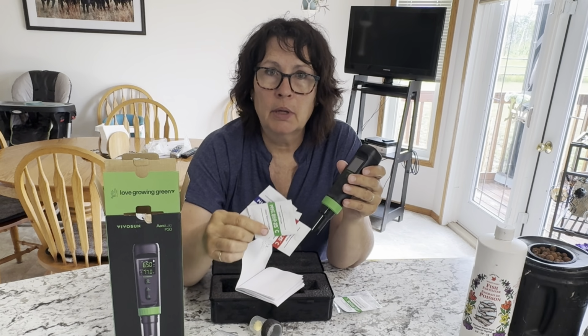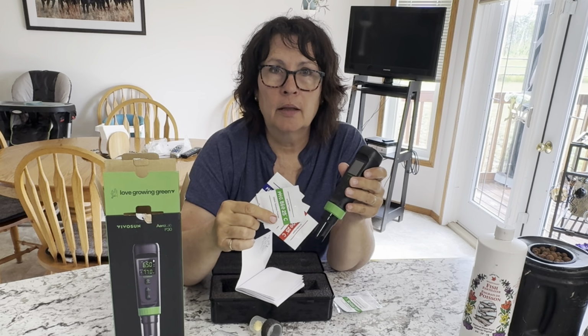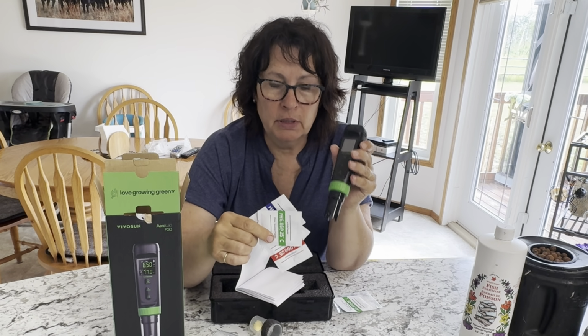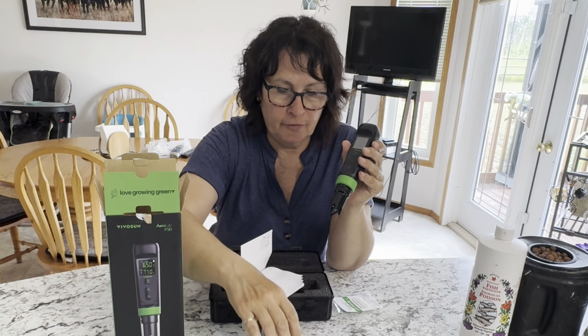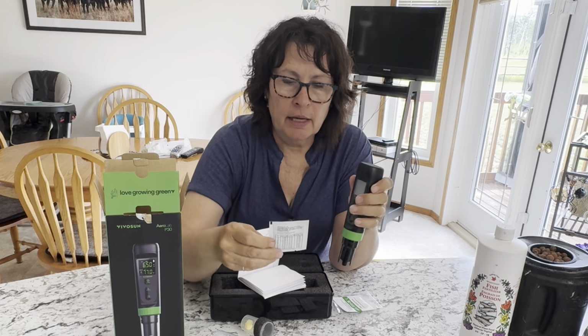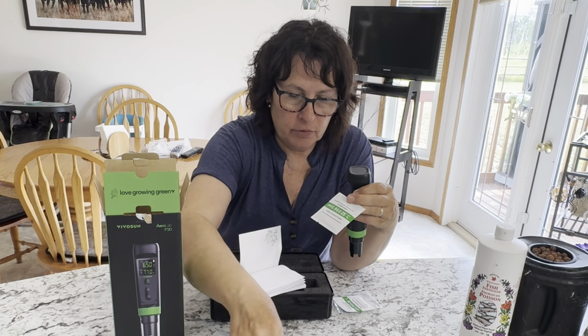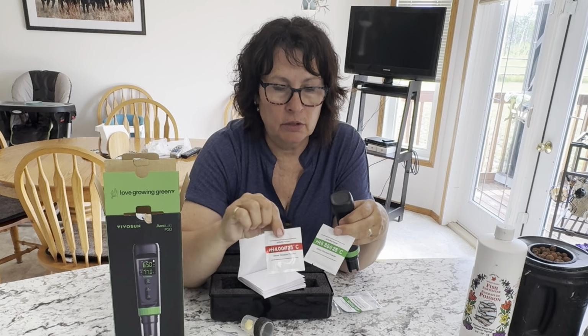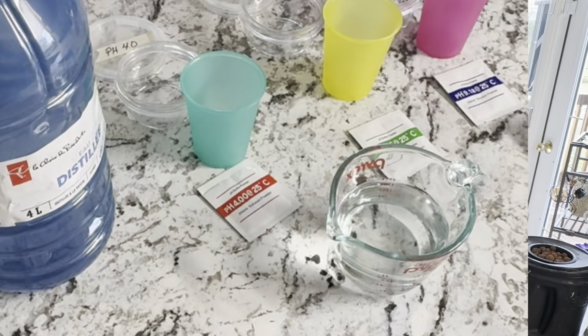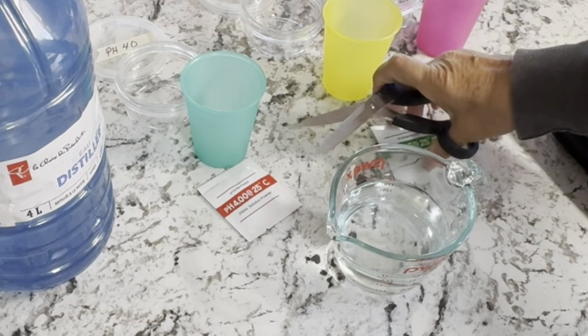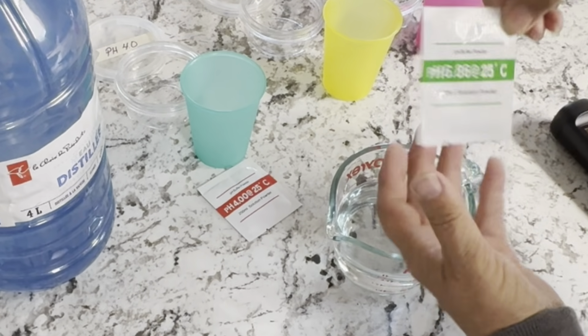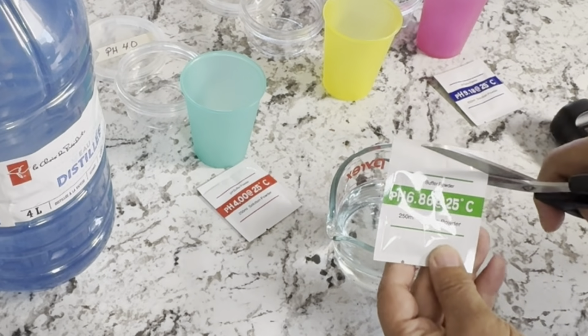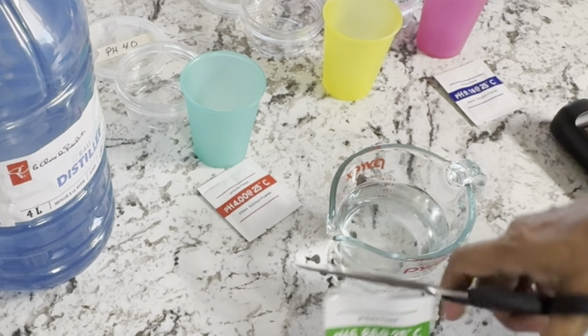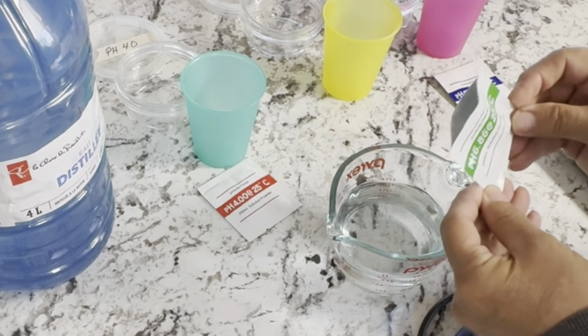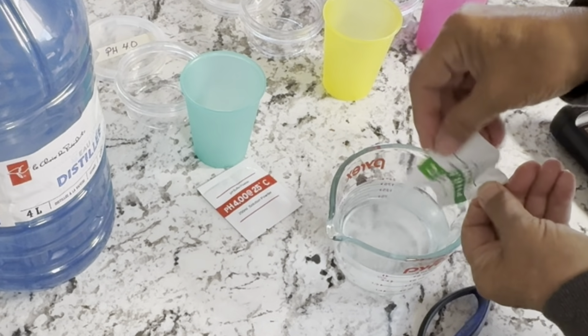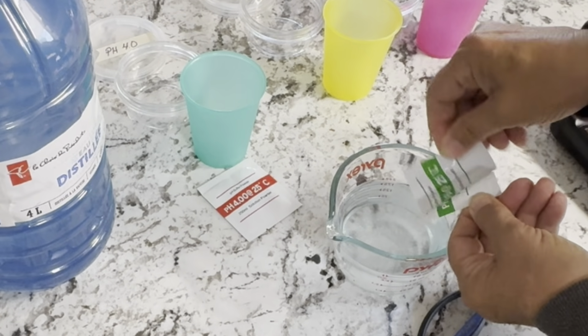So sometimes these come calibrated, but I always like to recalibrate my pH meters just to make sure that they are accurate before starting. And as far as the calibration, it comes with the 3 different calibration levels that you need to calibrate at. Okay, so I'm going to run you through the calibration process. So we are going to be mixing up some of this buffer powder. You start off by mixing it in a 250 milliliter solution of distilled water.